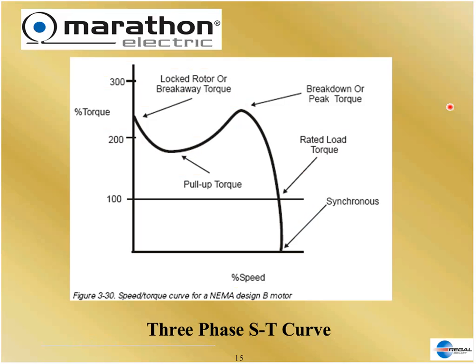Now, here is a speed-torque curve of a three-phase motor. We talked about speed and torque in the concept before. Torque is on this vertical axis, speed is on the horizontal. When the motor starts, because the wave will always start and run a three-phase motor, it will start at the point where the cursor is. Now the rotor is trying to accelerate and catch up to the synchronous speed, which is way at the bottom. And it just keeps accelerating until it gets to that point right there.